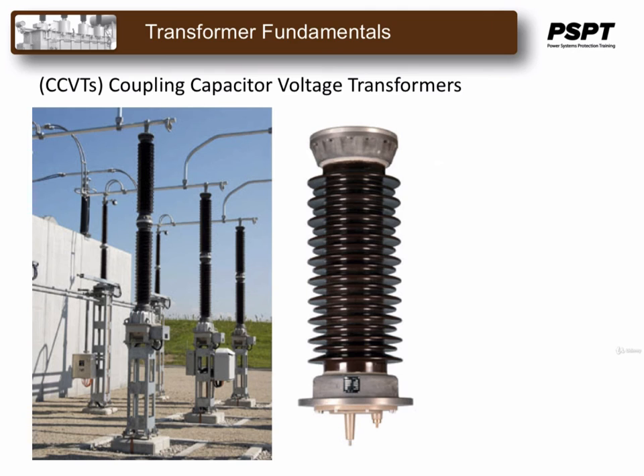Another type of potential transformer that's in common use today is the capacitor voltage transformer, or capacitor coupled transformer, and sometimes designated as a CVT or a CCVT. A capacitor voltage transformer is a transformer used in power systems to step down extra high voltage signals and provide a low voltage signal for metering or relaying operations.